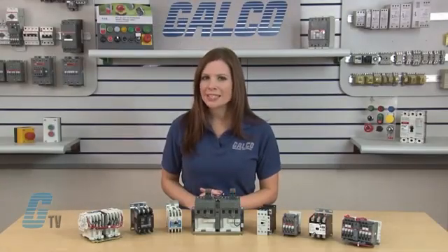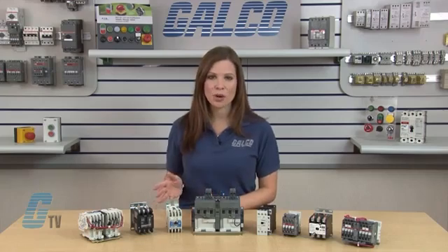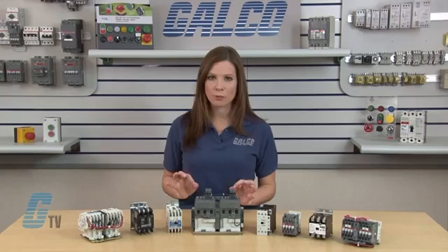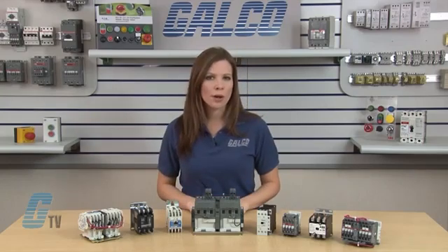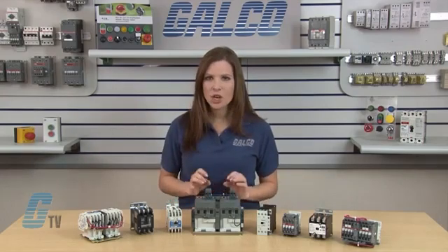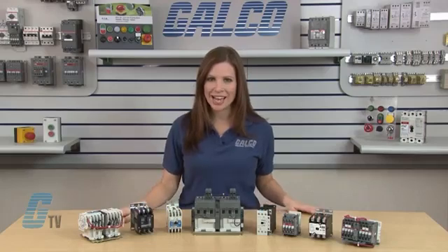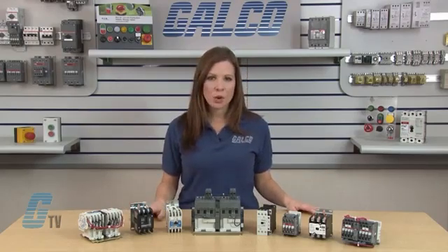To reduce power consumption in the contactor coils, latching contactors are used, which have two operating coils. One coil, momentarily energized, closes the power circuit contacts, which are then mechanically held closed. The second coil opens the contacts.